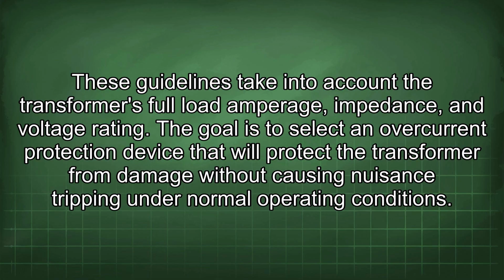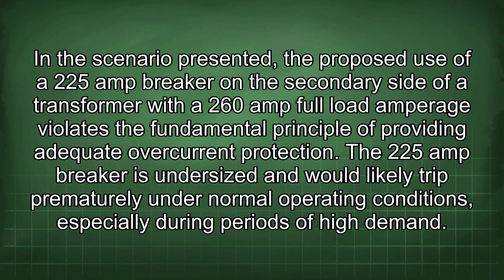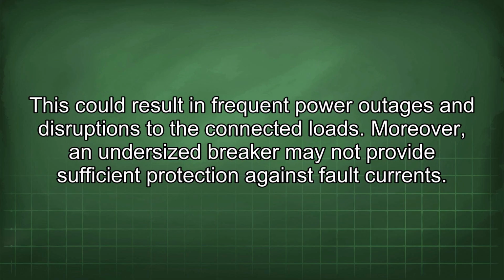under normal operating conditions. In the scenario presented, the proposed use of a 225 amp breaker on the secondary side of a transformer with a 260 amp full load amperage violates the fundamental principle of providing adequate overcurrent protection. The 225 amp breaker is undersized and would likely trip prematurely under normal operating conditions, especially during periods of high demand. This could result in frequent power outages and disruptions to the connected loads.